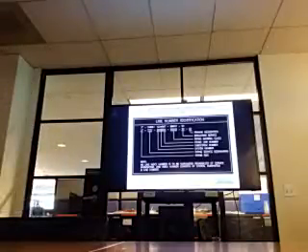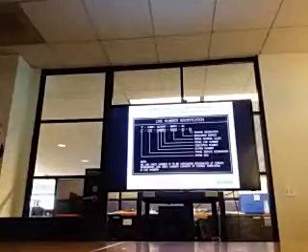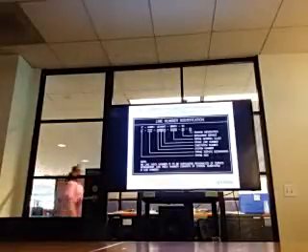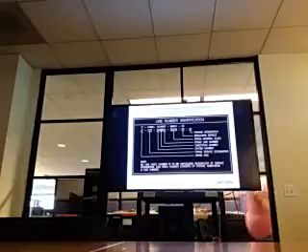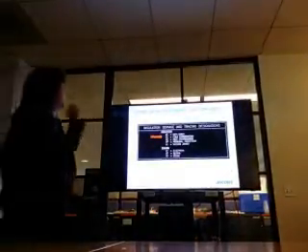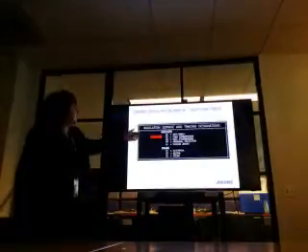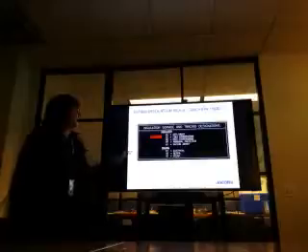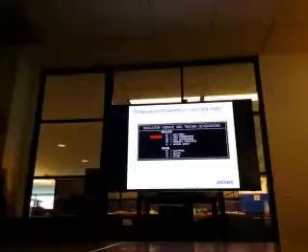It's a little more simplified, and if things change along the way, I think it has its advantages because it's a little less rework if anything changes. And these are just what those insulation codes are: anti-sweat, cold conservation, heat conservation, personnel protection, vacuum jacket. And then if it's trace, say it's outside and we're worried about it freezing, we'll say, okay, it's going to have electrical tracing on it besides the insulation, and that would be reflected in the line number.